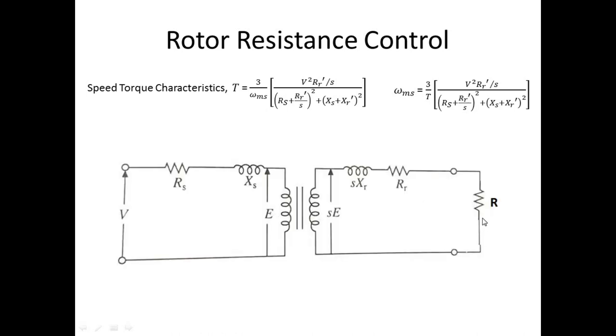Considering the equivalent circuit, we add an external resistance R to the rotor circuit, which adds to Rr. By varying this added resistance, we can vary the speed. That is the principle of rotor resistance control.